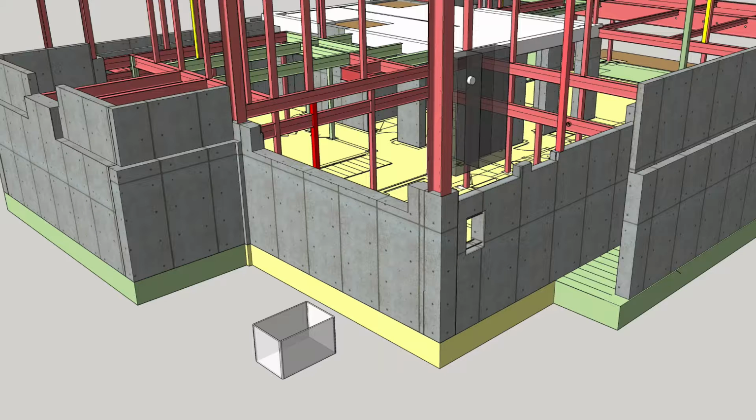As you are likely aware, the electrical utilities have specifications regarding the run of conduit through which they will pull their feed to the house service panel from their handhole. Typically, they require two 4-inch conduits, 48-inch radius sweeps, and not more than 270 degrees of sweeps in total.